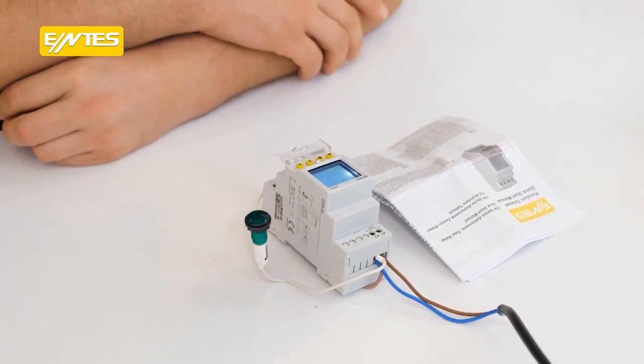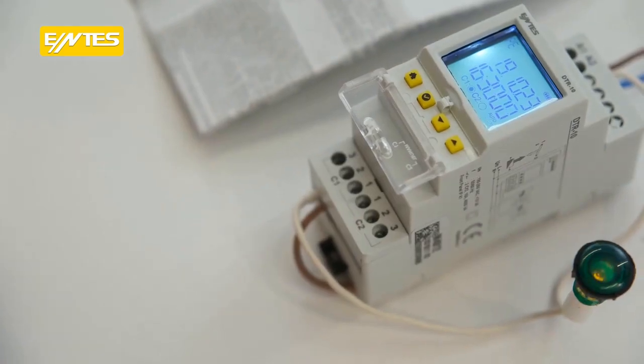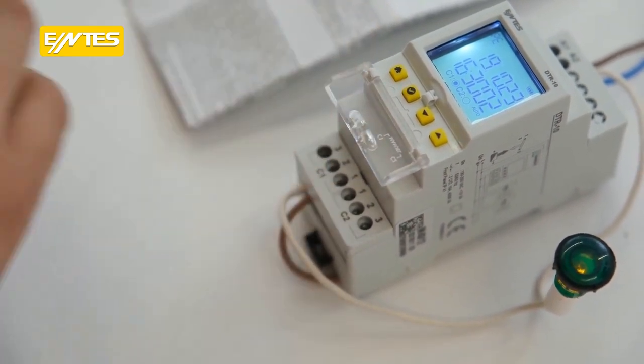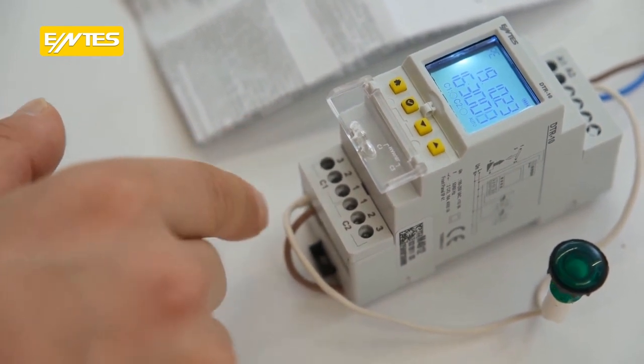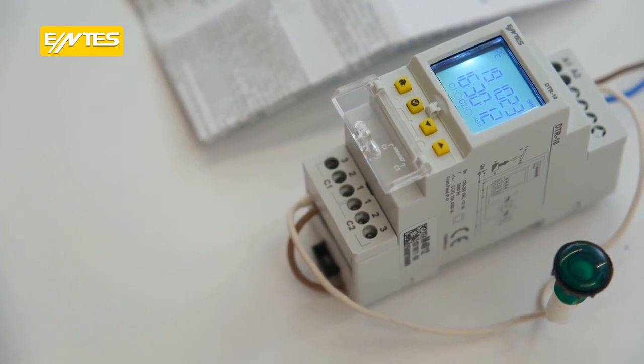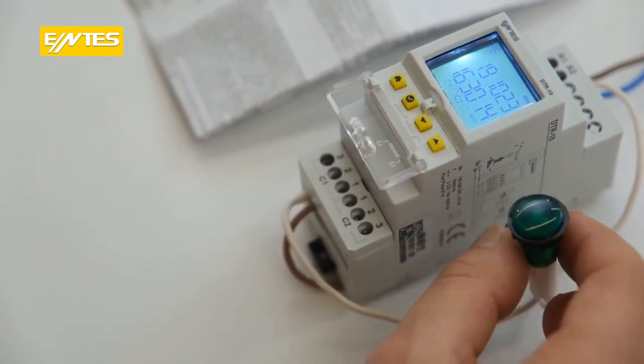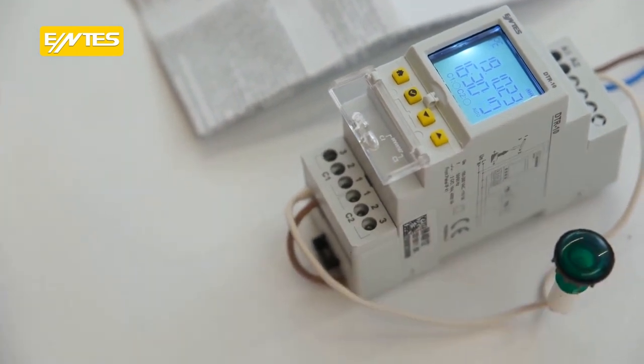Look, the device will output from C1 in around 7-8 seconds. We also mentioned in our user manual, don't use these as plug and play. They're remote control devices. Definitely, a power contactor must be connected to their output to prolong its lifespan for the relays. Look, it just gave us the output. Again, time has passed and the energy has been cut. It's like this.